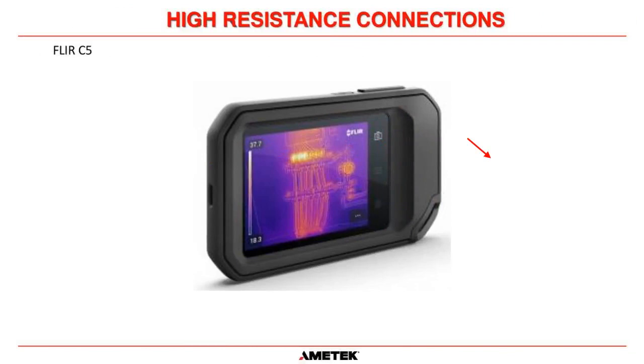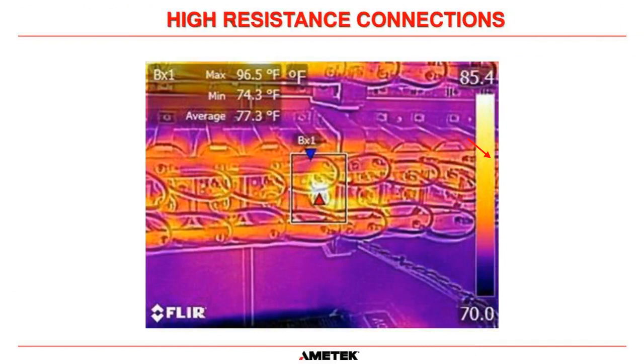Well, how can we prevent that? Well, all of the Ametek solid-state controls field service guys, absolutely every single one of them, carry a FLIR C5 infrared camera, okay? And it is an industrial grade infrared camera from one of the most renowned makers in infrared cameras, FLIR. And here's a prime example of what they find. Every PM that one of our guys performs, they have to take pictures inside the UPS of certain components to look for high resistance connections. And in this picture here, they took a picture of the AC capacitors inside the UPS.